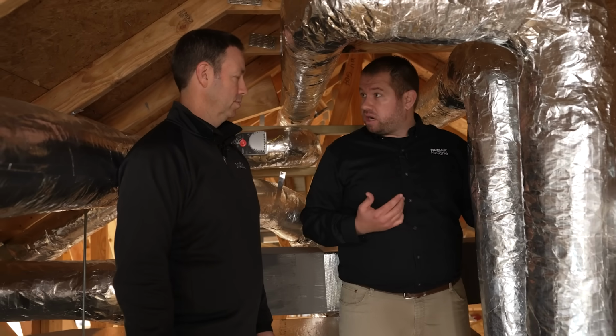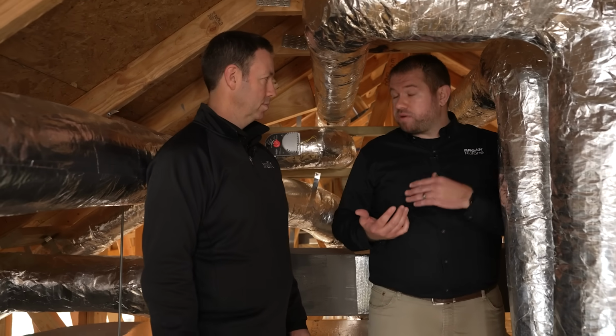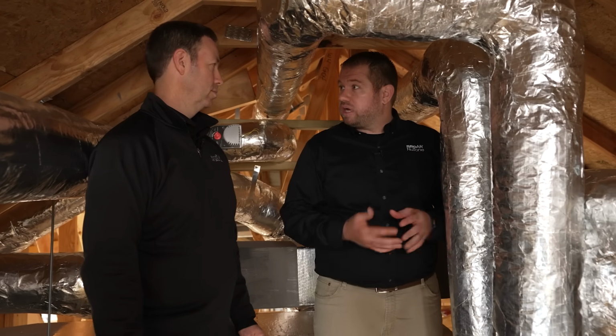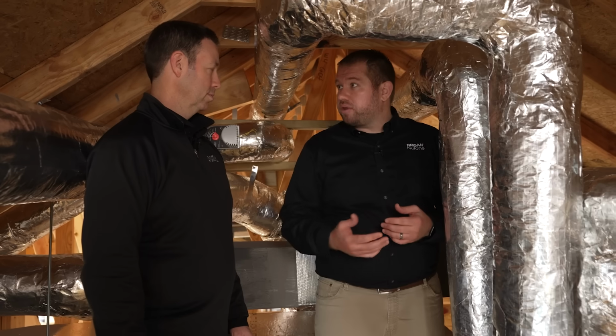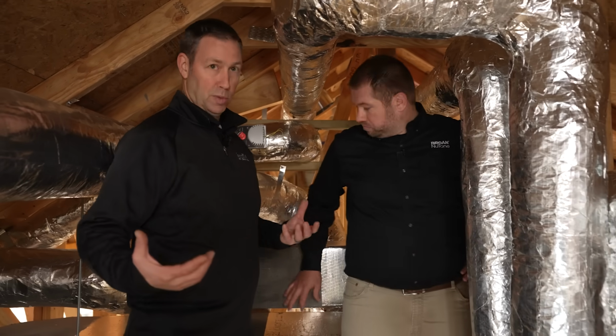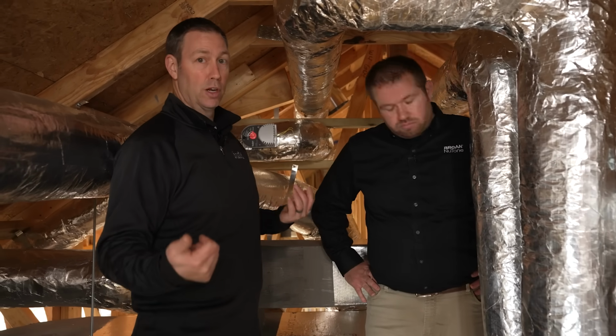So the difference between the outside air and the stale air we're removing from the home, that difference is what we're going to recover. With an ERV, on top of the sensible heat, we're also going to retain latent heat, or moisture. So particularly in the hot, humid south here in Austin, we're able to take advantage of that core, retaining some of that moisture and taking it out of the airstream entering the home. So in general, I tell people if you're in the south, you absolutely want an ERV.